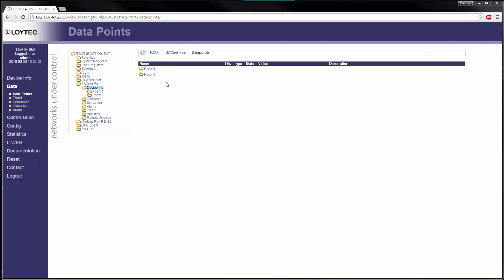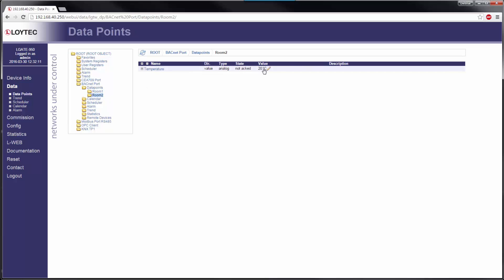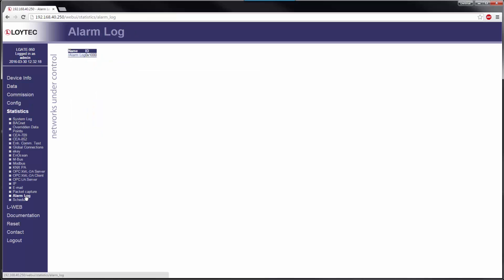LOYTEC devices now support the BACnet event message text property of an alarmed object, which allows retrieving the messages also after a reboot of an alarm client. Alarm logs have also been updated to support the new maximum length.